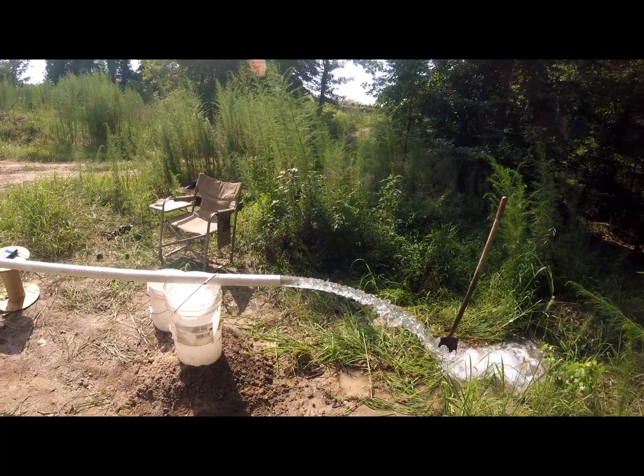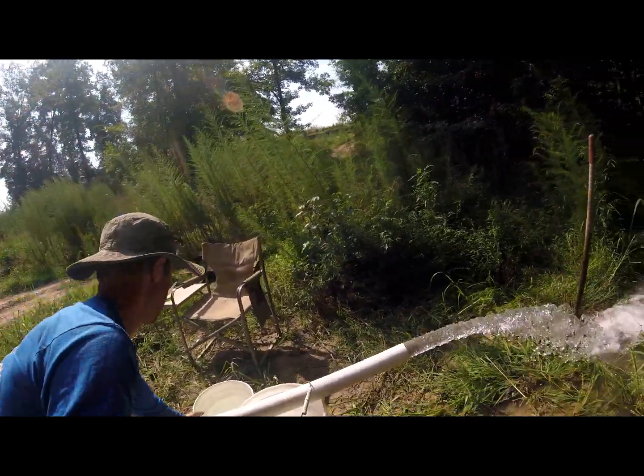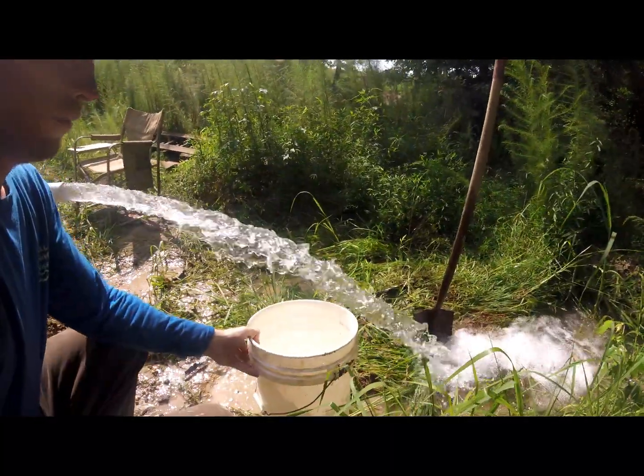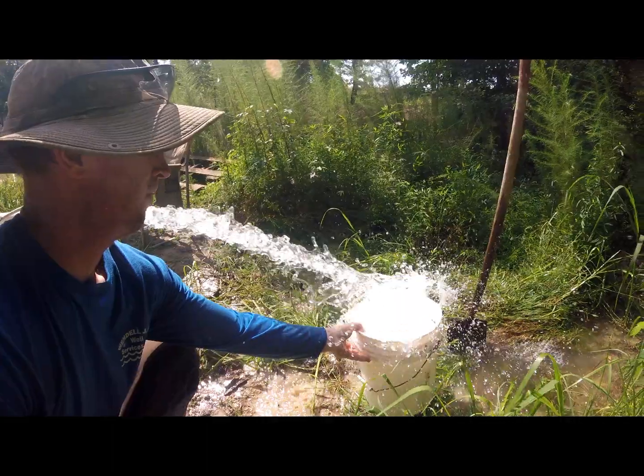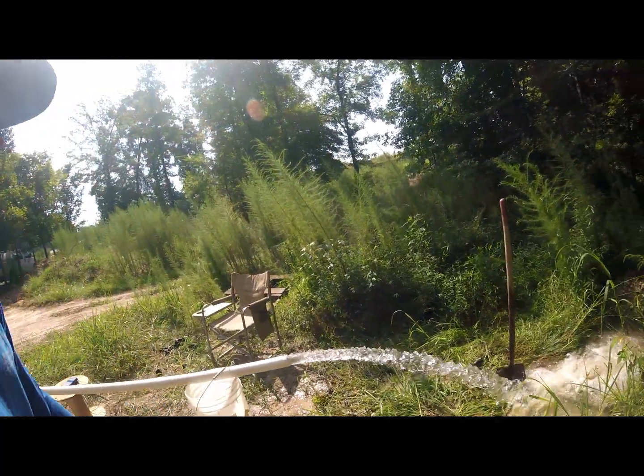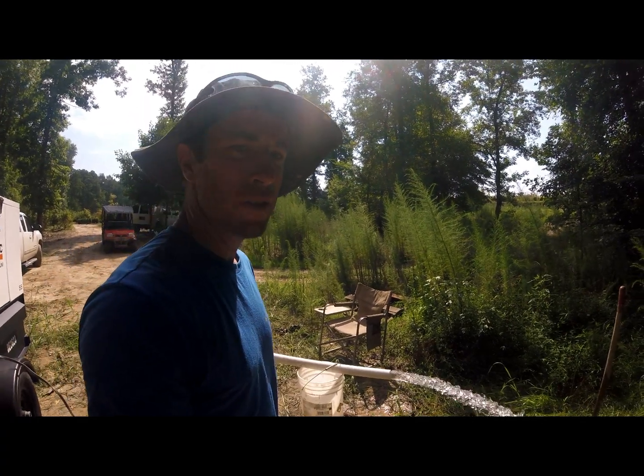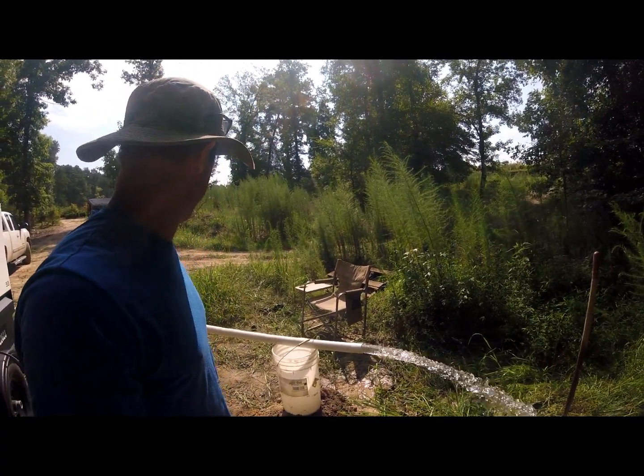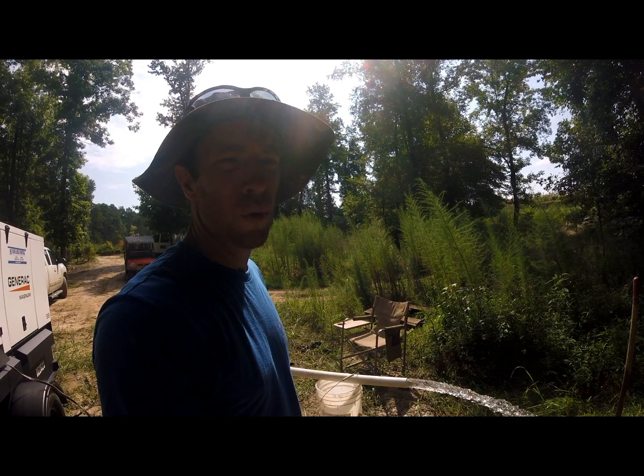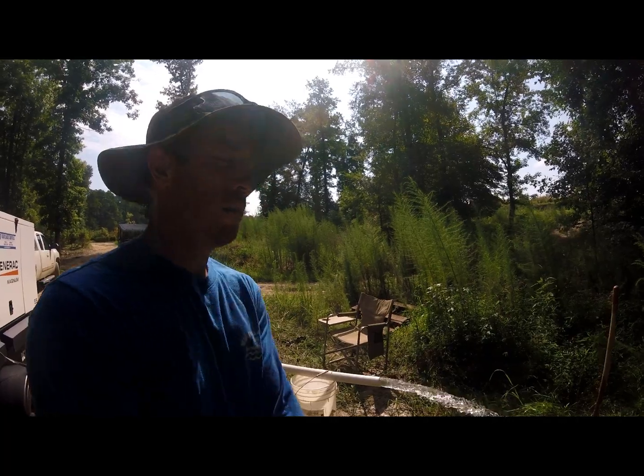Sure enough, look at what it's pumping — about 150 gallons a minute. You can see what's going on here. Sorry for the poor camera quality. Getting after it, one hour in. Long ways to go, so we'll keep on going. Been checking the water level — it's around about 120 feet, started at 50 feet. It's strong — stay tuned, I'll continue to keep you updated.